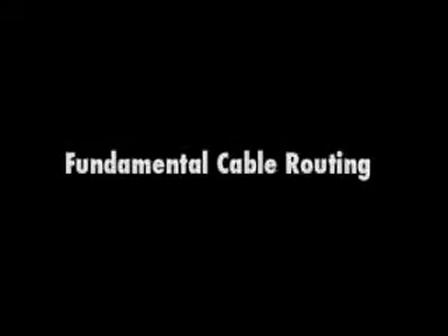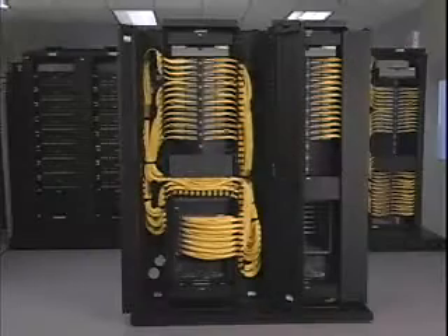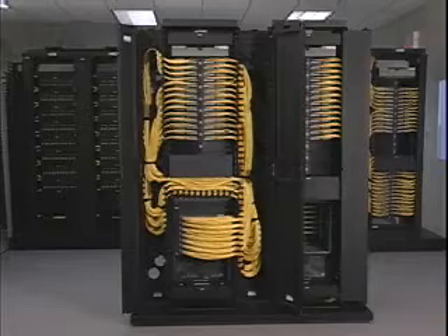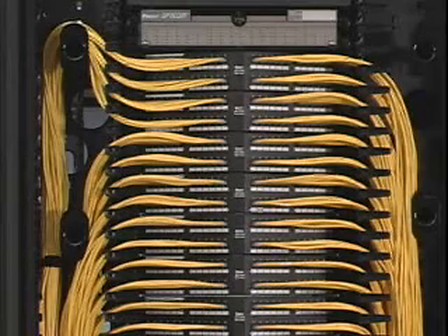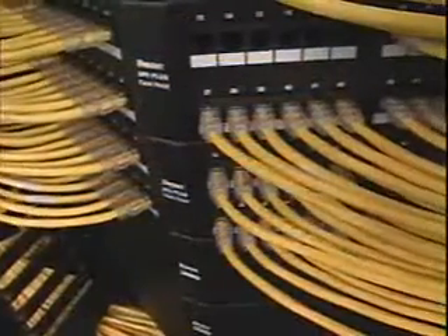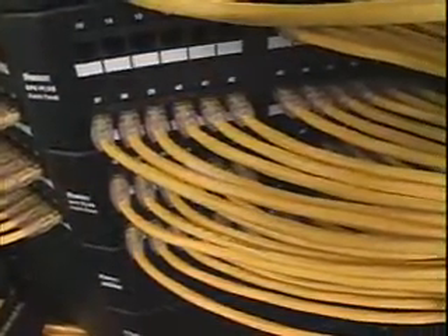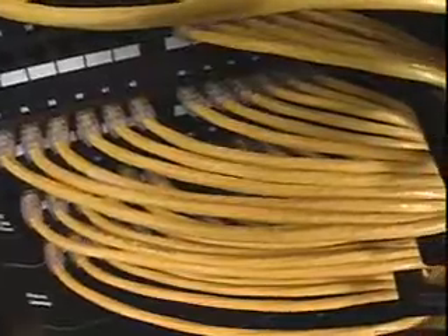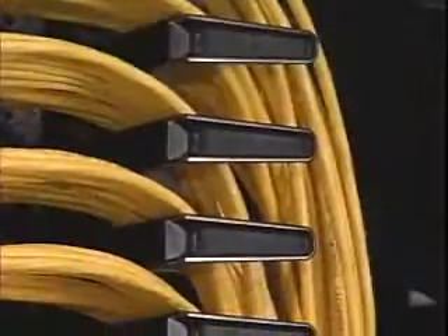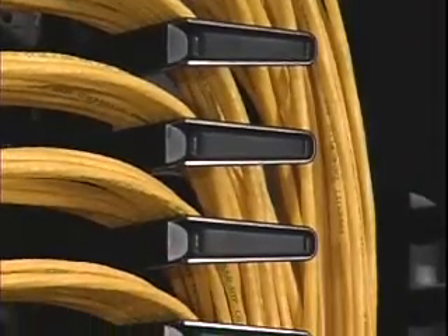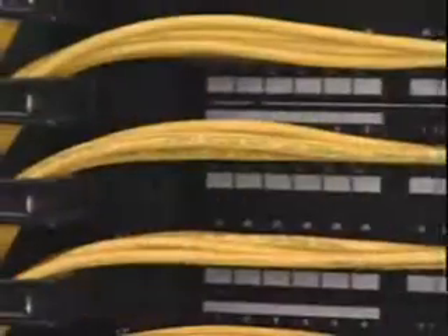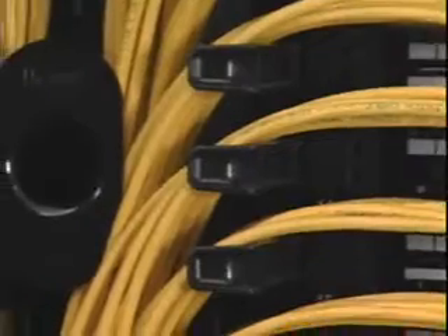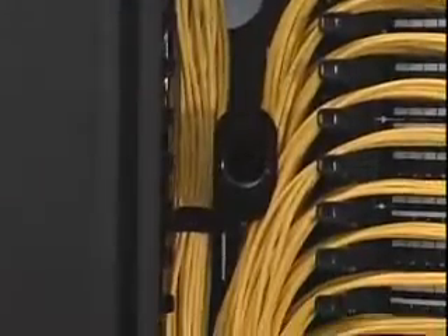Fundamental cable routing. After all system components have been installed, cabling can begin. A few basic guidelines for patch panel routing are: patch cords are to be routed directly horizontally from the patch panel into the finger opening that is aligned with the patch panel rack unit. The PatchRunner cable management fingers have been designed to support patch cords as they transition to the vertical pathway, eliminating the need for horizontal cable managers.